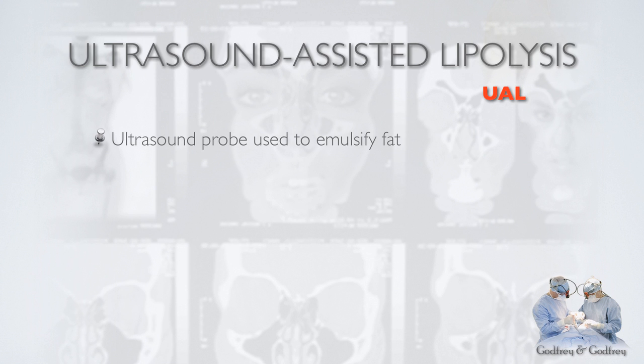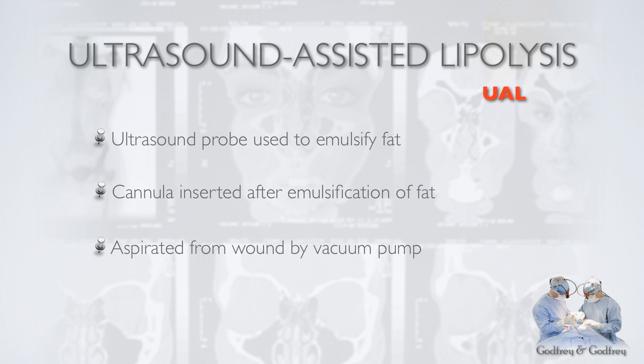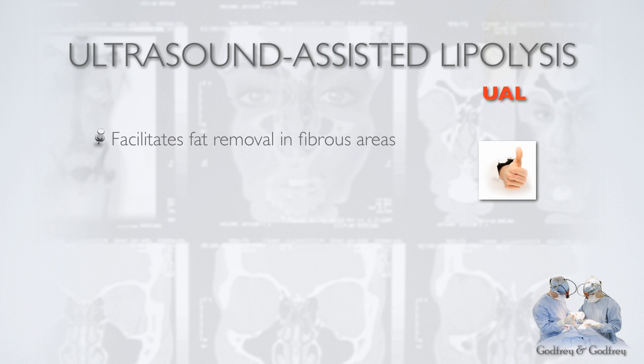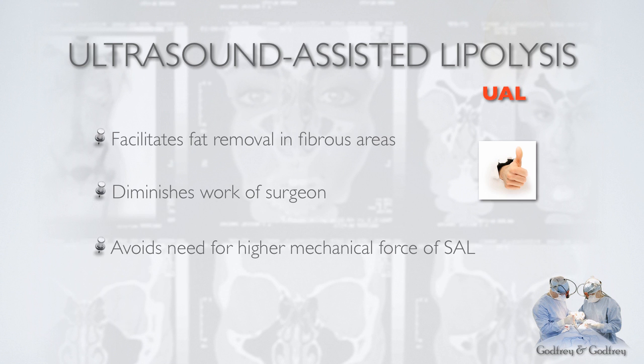Ultrasound-assisted lipolysis, or UAL, employs an ultrasound probe to emulsify fat. This is inserted beneath the skin as the first step. A cannula is then inserted after the fat has been emulsified, and the fat is aspirated from the wound by a vacuum pump. An example of this is called Vaser. This technique facilitates fat removal from fibrous areas and diminishes the work of the surgeon. It avoids the need for higher mechanical forces in SAL.